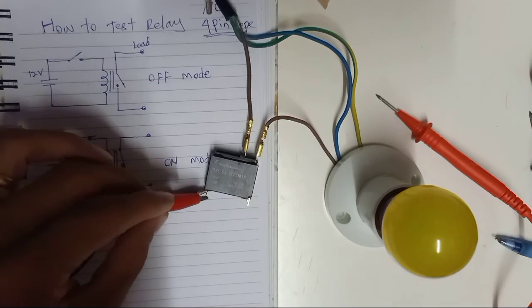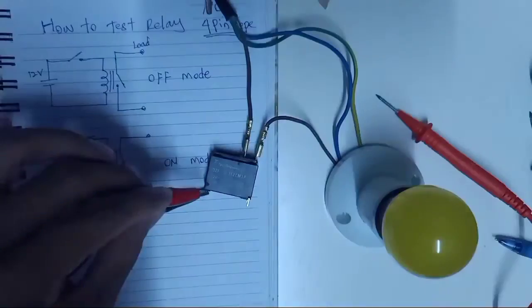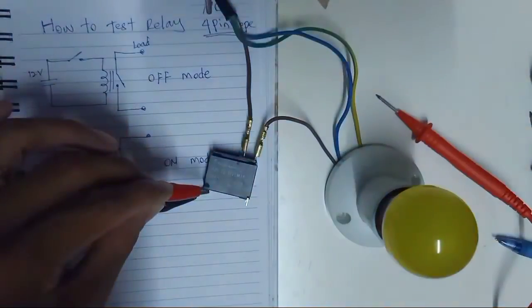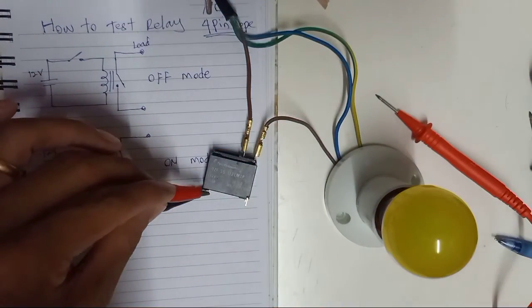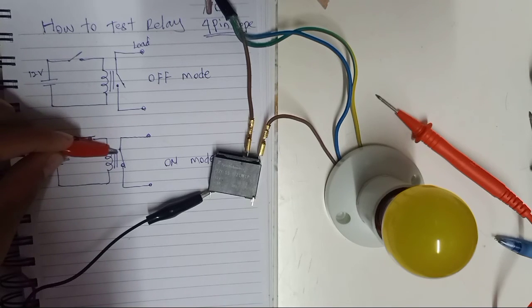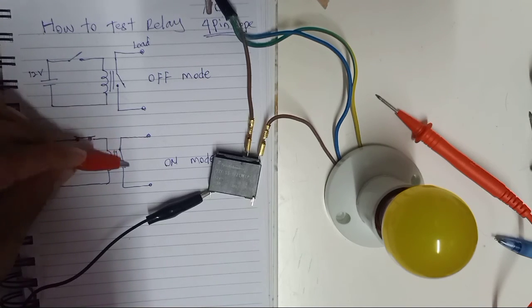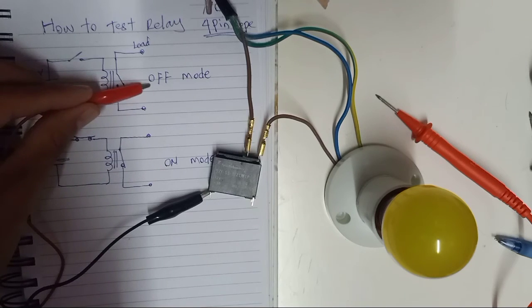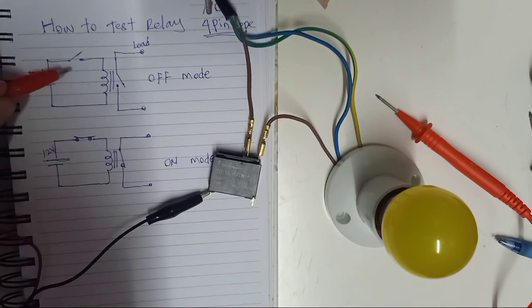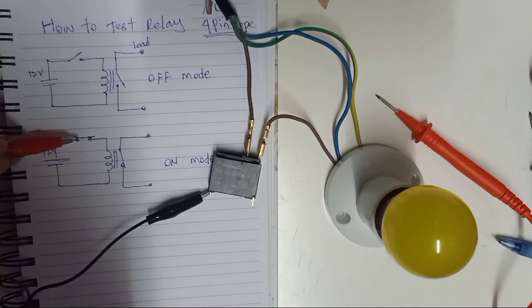Then you turn on the AC and trigger the supply here. The relay is on. This relay is in good condition. You can hear the sound. The moment the trigger is supplied here, the relay coil is on and conducting, and the loop is turning on. If you don't supply here, the relay is always off. This is the normal condition. We call this one normally open relay. After we supply the 12 volt, then it's turning on.